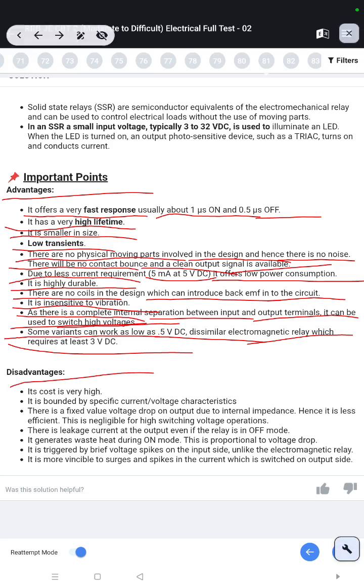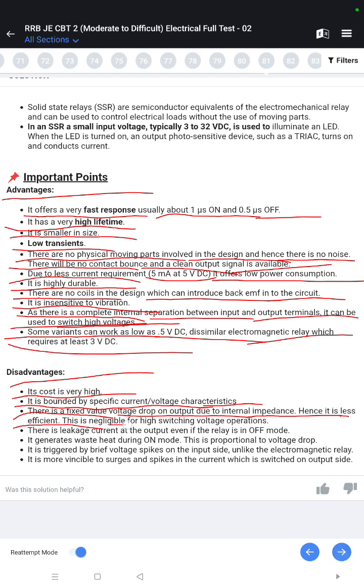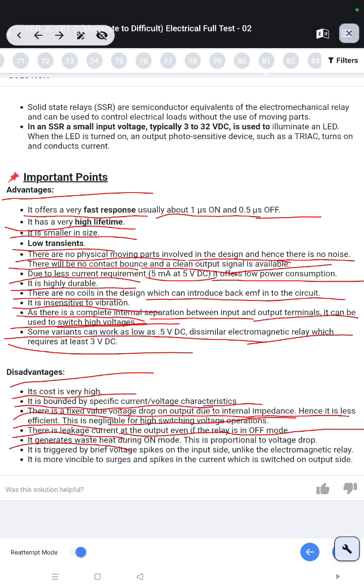Disadvantage: its cost is very high. It is bounded by specific current and voltage characteristics. There is a fixed value voltage drop on the output due to internal impedance, hence it is less efficient. This is negligible for high switching voltage operation. There is leakage current at the output even if the relay is in off mode. It generates waste heat during on mode, which is proportional to the voltage drop.